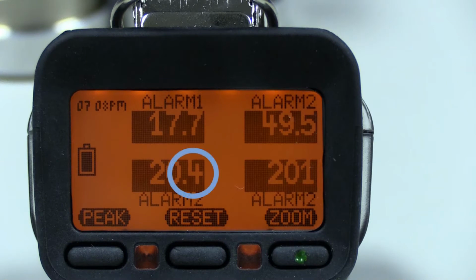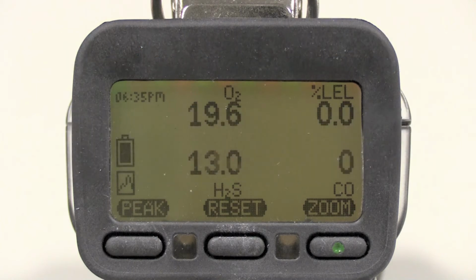Remember, there is a decimal point in both the H2S and the LEL reading. Where to set the gas alarms depends on where the instrument is used, the applicable regulations, and company policy. Certain jobs and activities may require special precautions and procedures. Consult your employer or government agency to verify that the alarm settings are correct.